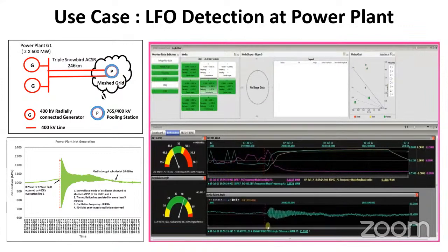These were quite long lines, around 246 kilometers. Based on the state, it is known that without PSS tuning, stability cannot be ensured because the angular separation when one line trips is quite high. As explained earlier, if there is a large impedance and weak connectivity, the oscillation observed from the generating station will be quite huge for that plant. You can see the plant operating at 1000 megawatts.